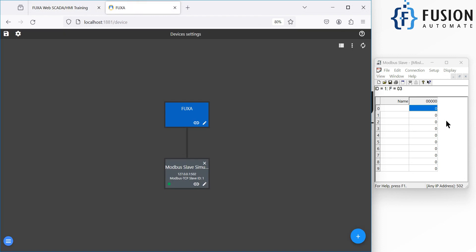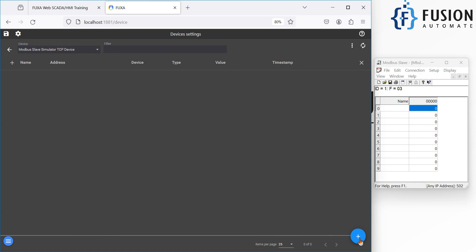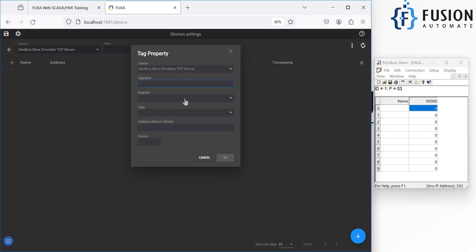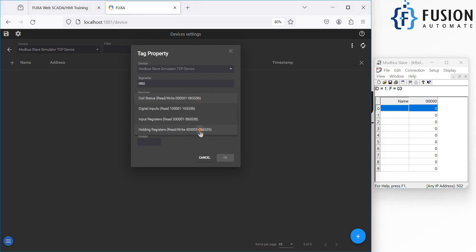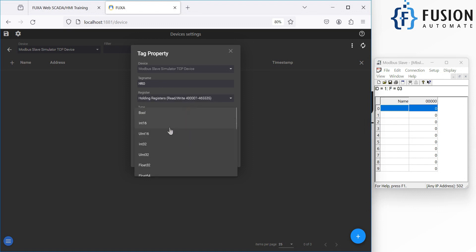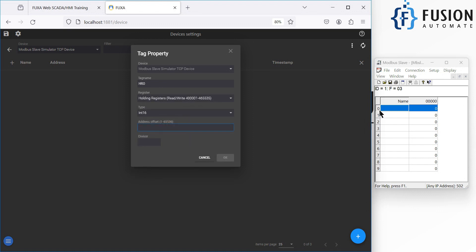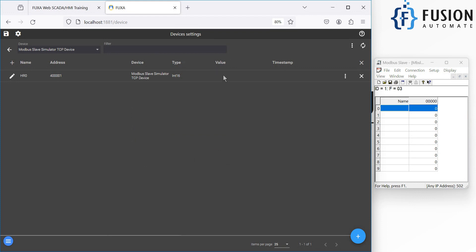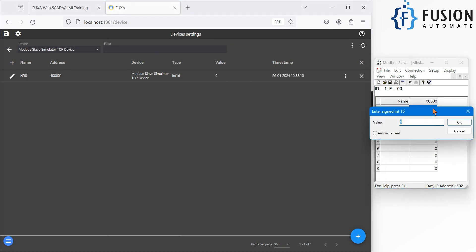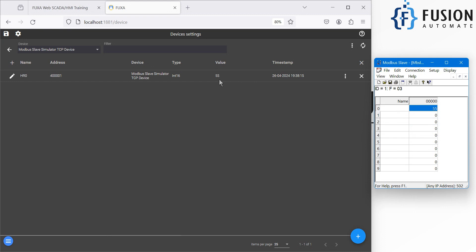To create a tag for your Modbus TCP device, click the 'Edit Device Tag' button, then click the plus to add a tag. The tag name is 'Holding Register 0', the register type is Holding Register, the type is Integer 16, and the address is 1. Press OK. You'll see the value is zero. If I change the value to 55 in the simulator, you can see it updates to 55 here in FUXA SCADA.